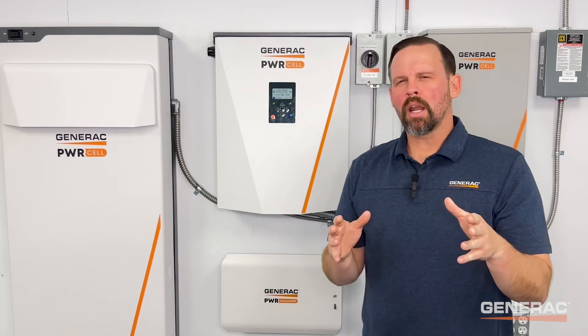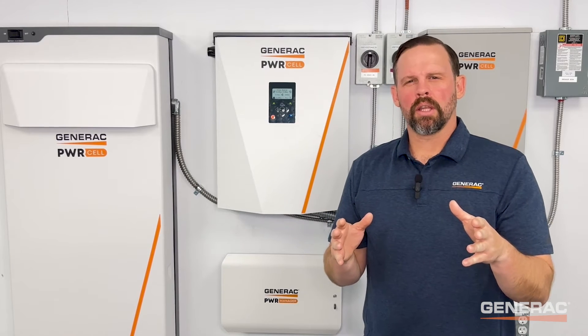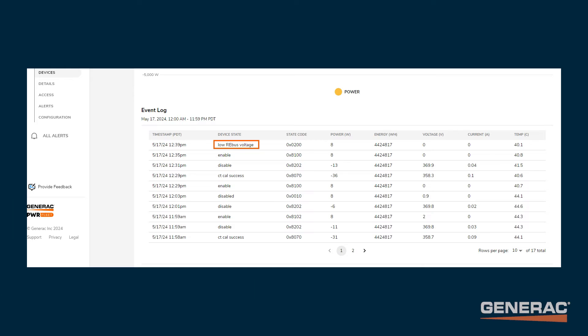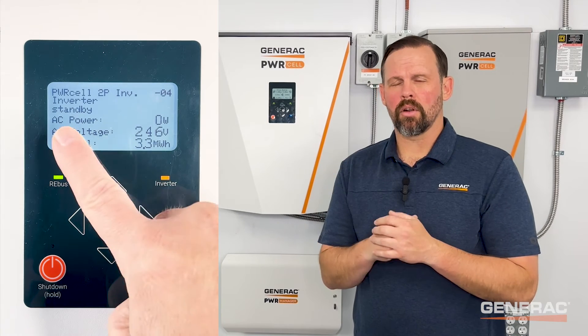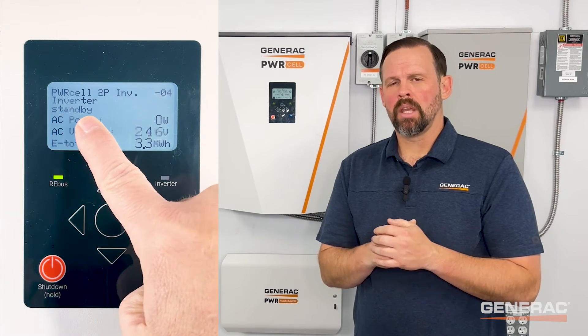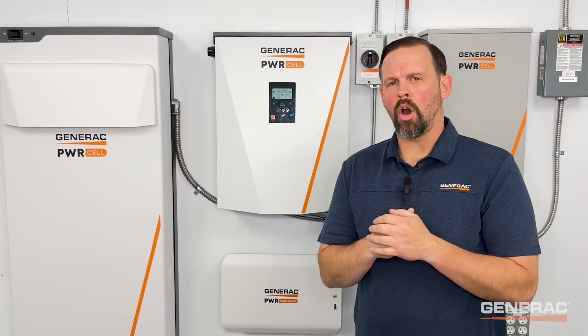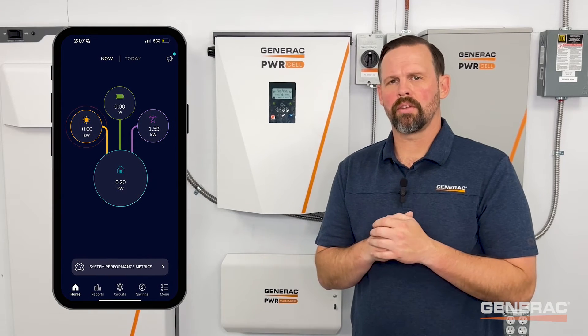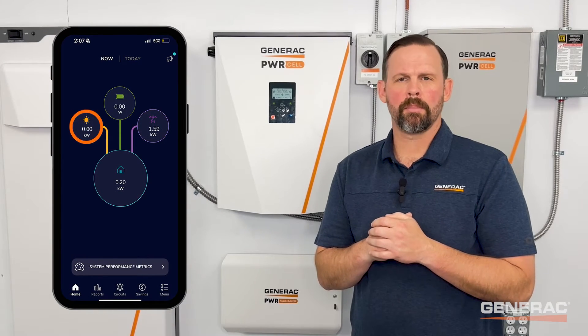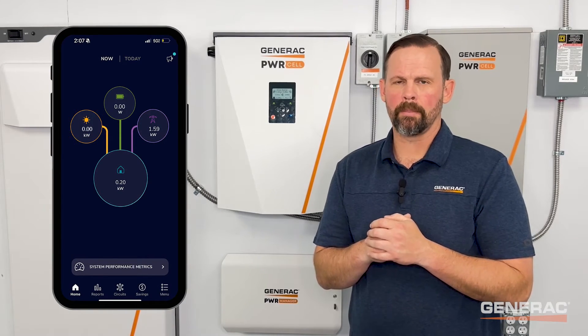If the inverter cannot connect to the grid, you will see standby, waiting, or low rebus voltage displayed in PowerFleet and locally on the inverter screen. Additionally, the homeowner may notice they have no production from their system in their PowerView mobile app.